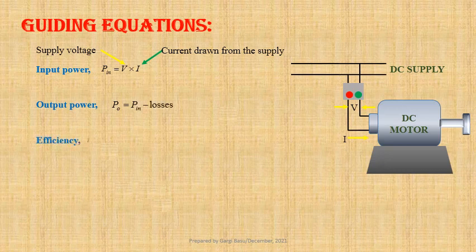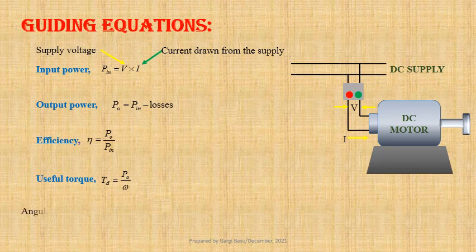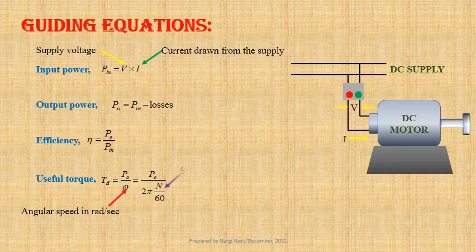Efficiency of the motor: eta equals P_o divided by P_in. Useful torque: T_d equals P_o divided by omega, where omega is the angular speed of the motor in radians per second. T_d may be written as P_o divided by 2*pi*N/60, where N is the speed of the motor in revolutions per minute. Therefore, output power P_o equals T_d into 2*pi*N/60.